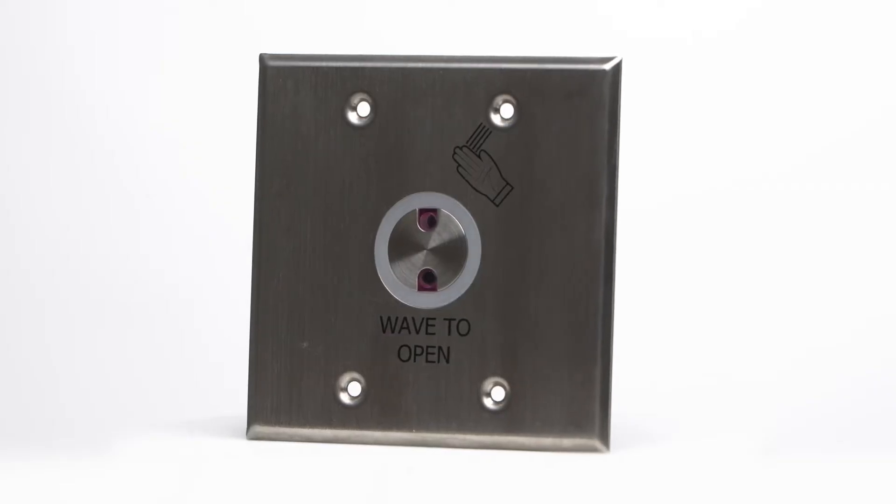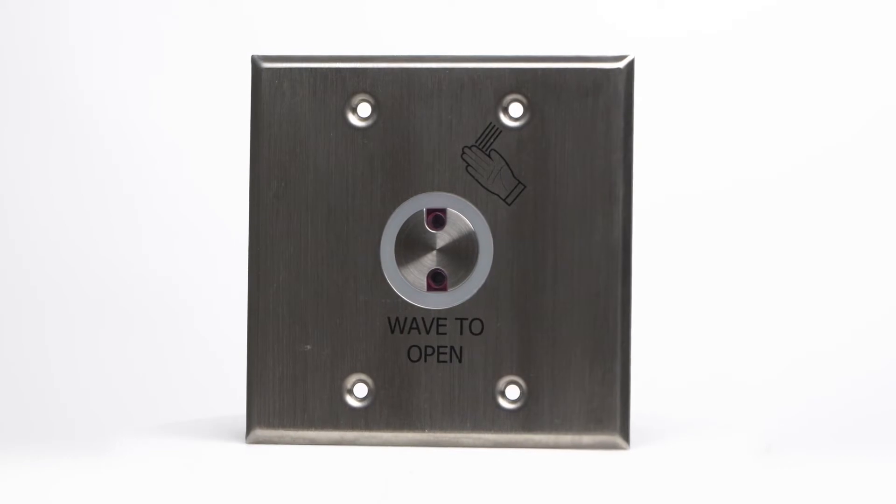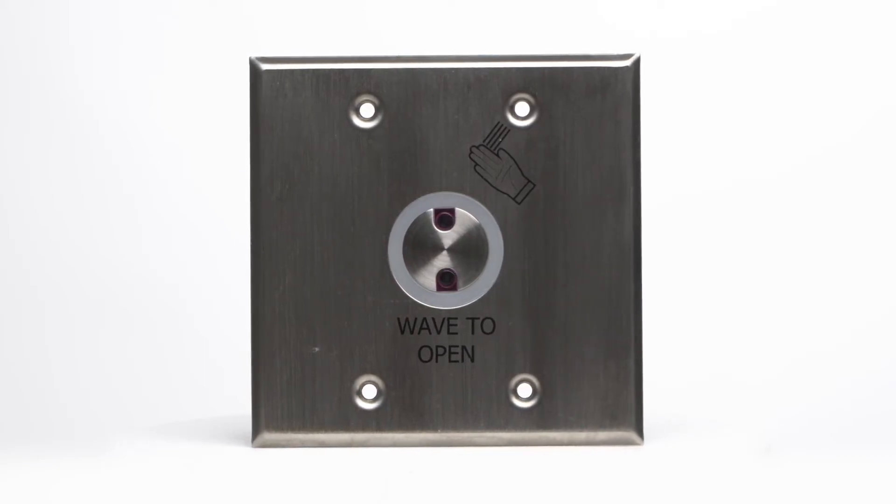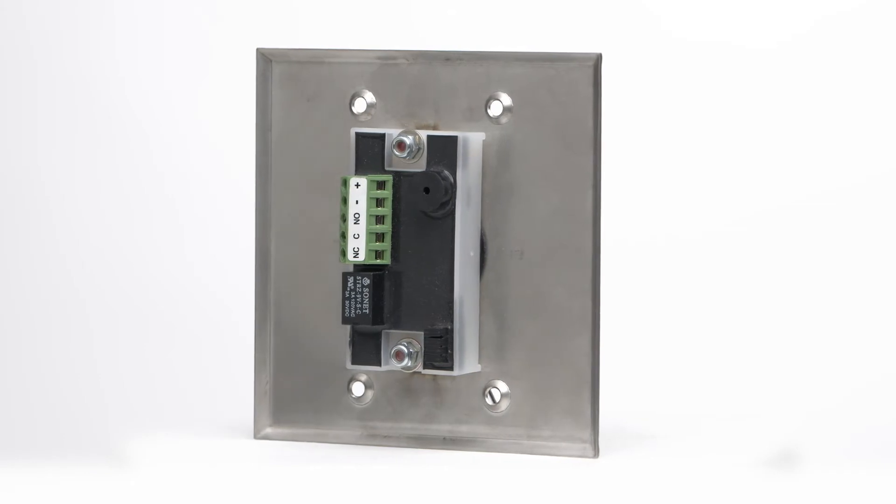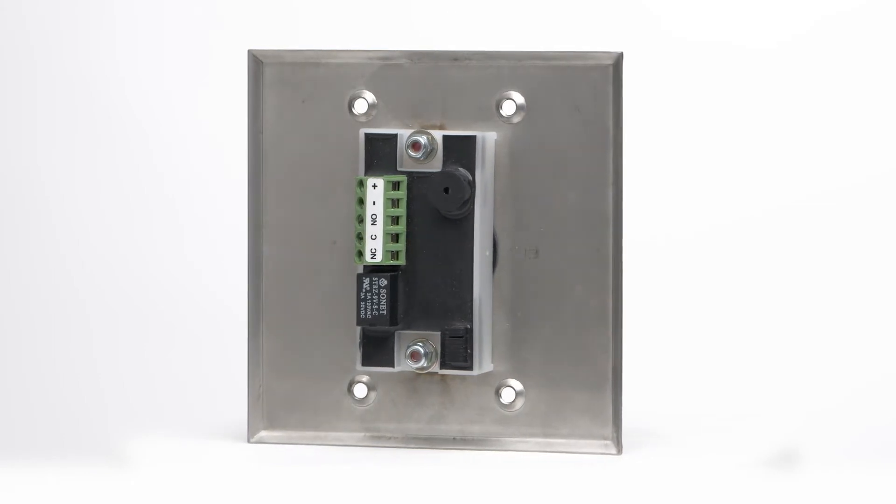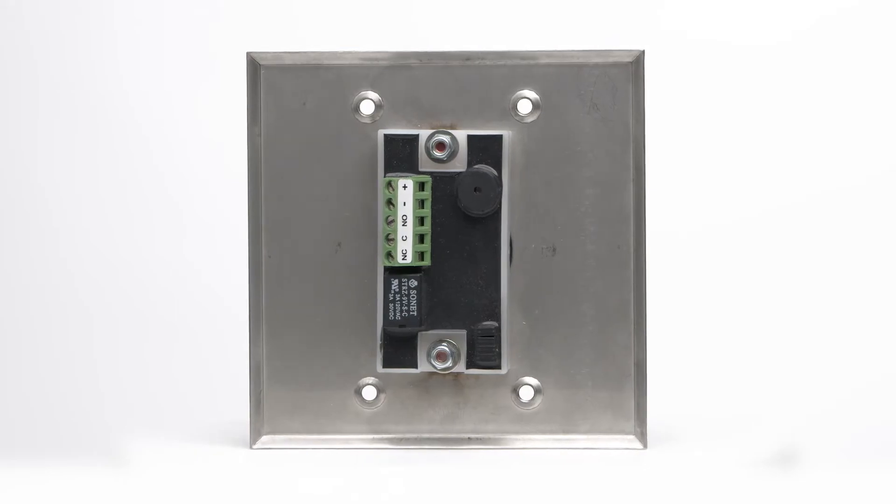The wave-to-open switch requires 12 to 24 volts of DC power as well as dry contacts for operation. So the existing two conductor wire will need to be replaced with a four conductor wire to power and operate the wave-to-open switch.